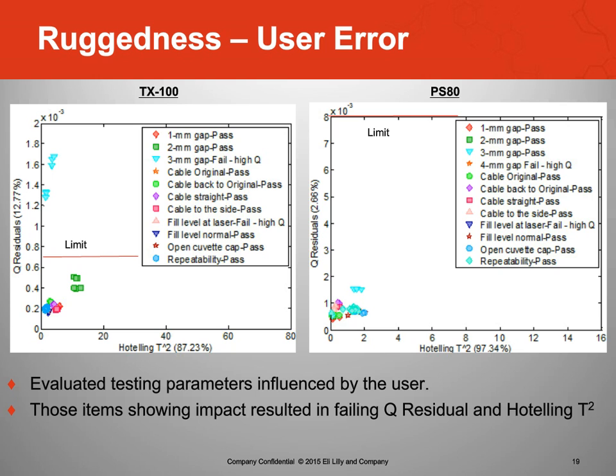This case wasn't the same for polysorbate 80. They could tolerate about a 3 millimeter gap. Even 4, which isn't shown here, does fail. It's off scale. I just decided not to show it because I'd have to zoom out quite far. We also looked at cable position. Fiber cable is pretty susceptible to positioning and its impact on throughput. So we wanted to make sure that if the analysts were moving the cable around to reposition it, it wouldn't have any impact. And we showed very little impact on both Triton and Tween.